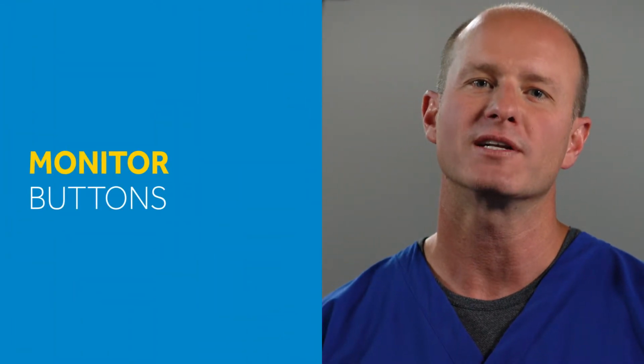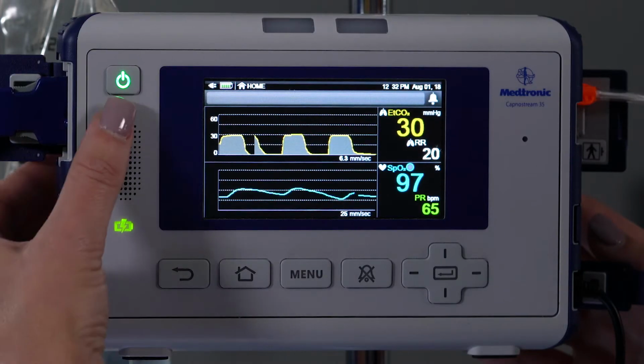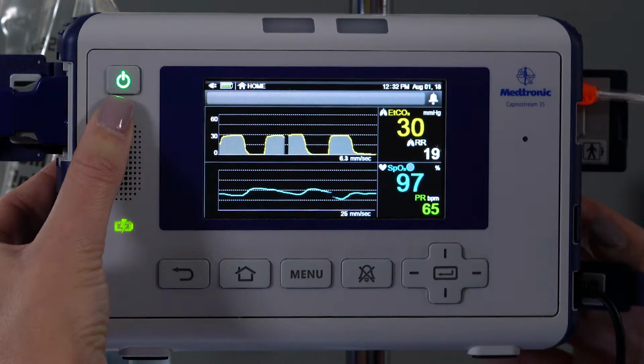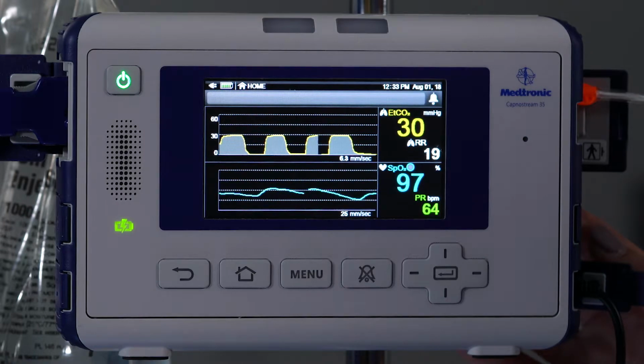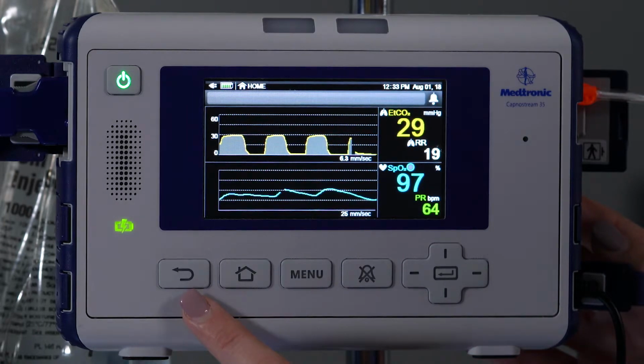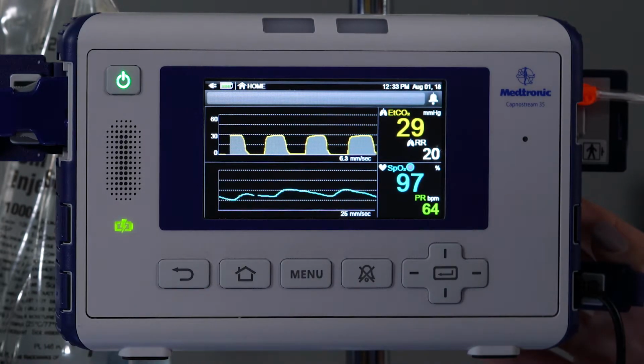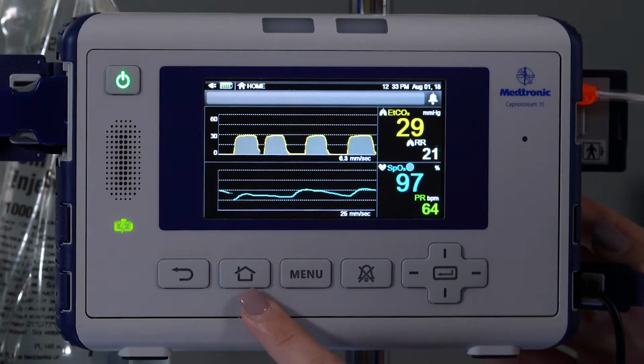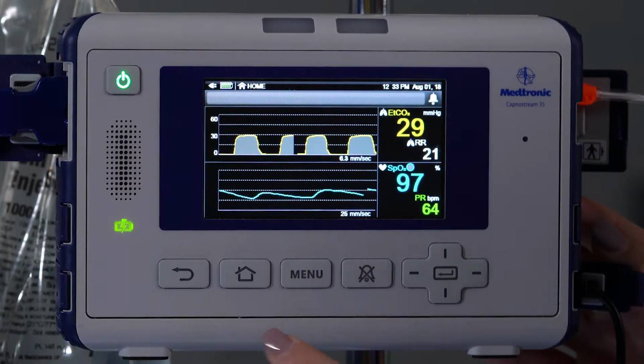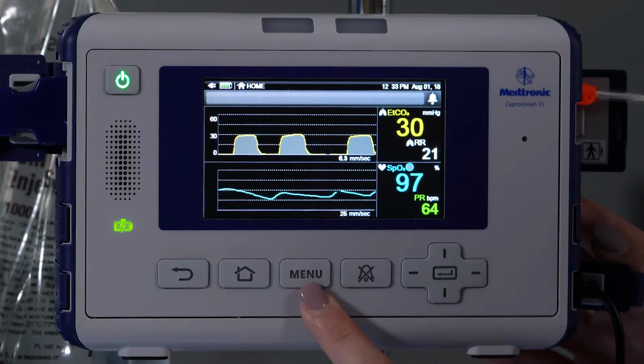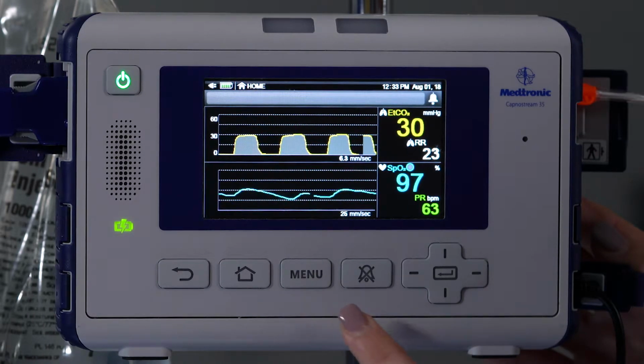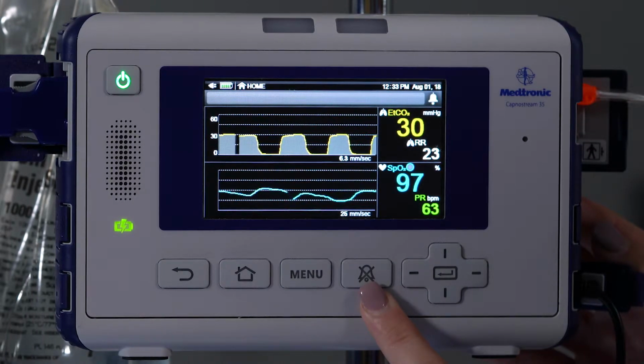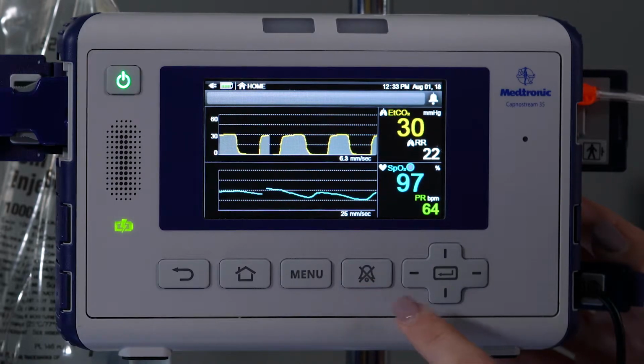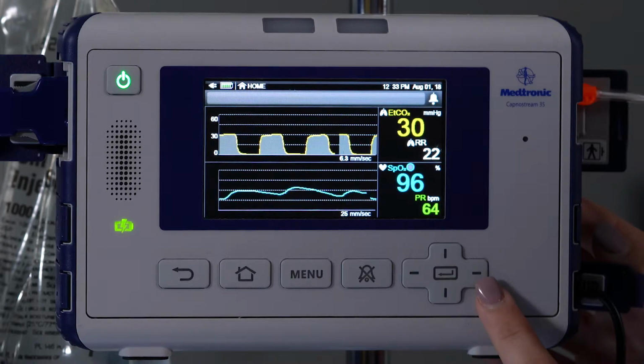Now, let's go over the buttons on the device. Here is the monitor power button. Simply press it to turn on the Capnostream 35 monitor. The back button will return you to the previous screen. The home button returns you to the home screen. The menu button opens a menu of options. Pressing the alarm silence button will stop alarms for 2 minutes. The enter button and directional arrows can be used for navigation and menu selection.